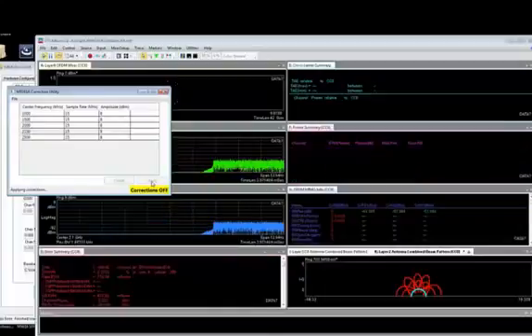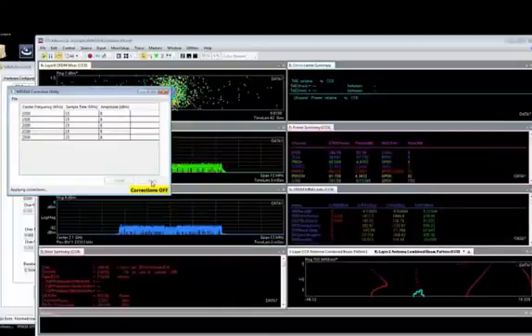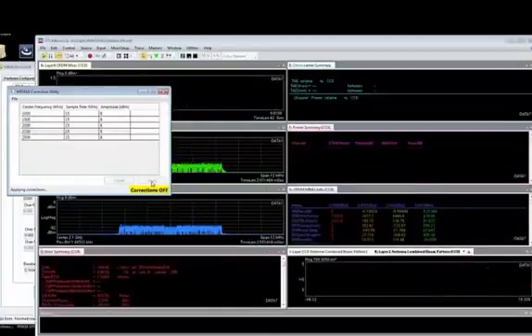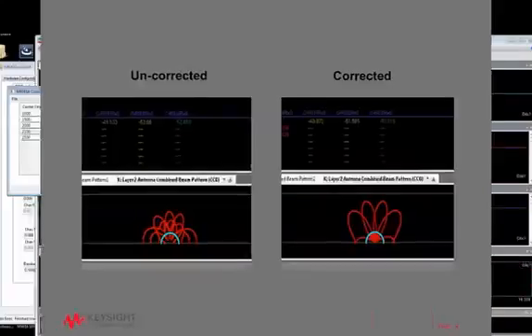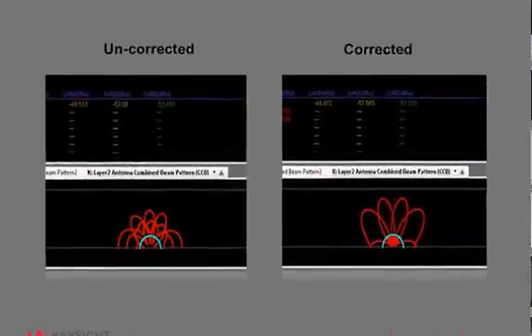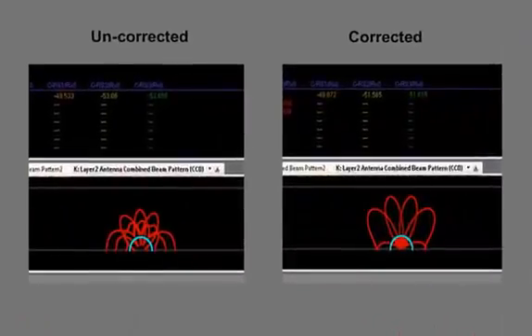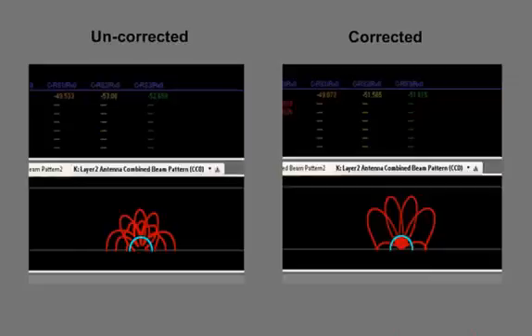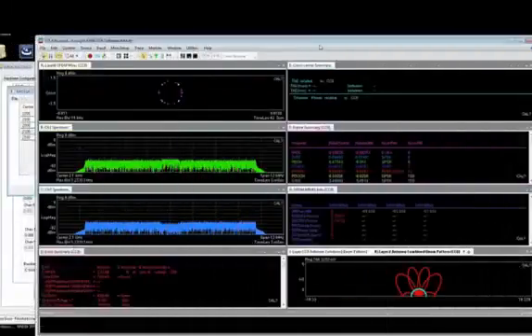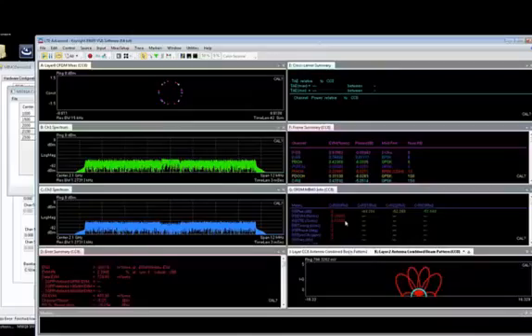Once the corrections are applied, we can now see the beam patterns with the corrections. Notice that there is a significant difference in the beam patterns with and without the channel-to-channel corrections. This showing the importance of calibration of your beamforming measurement.